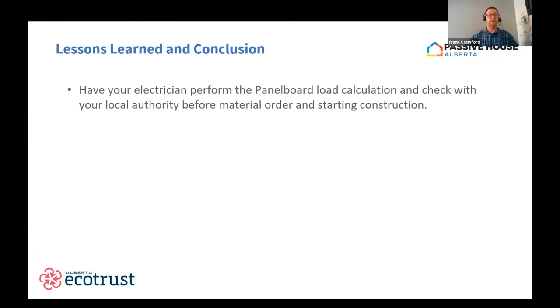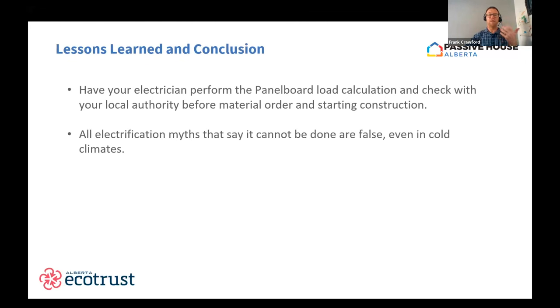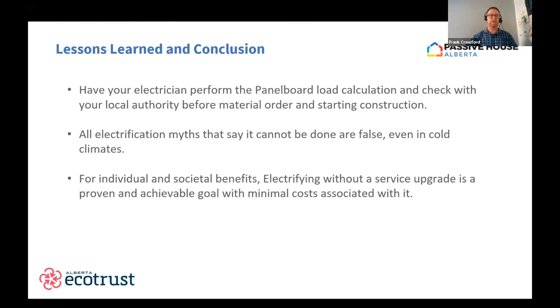So, as a conclusion, have your electrician perform that panel board load calculation early and check with the local authority to make sure that everything is acceptable to them before you start construction and order materials. All of the electrification myths that say it can't be done, even in cold climate Alberta, are false. It can be done. It has been done. We will continue to do it. And for both individual and societal benefit reasons, we want to make sure we are electrifying without a service upgrade, which is a proven and achievable goal for the minimized cost associated with it.